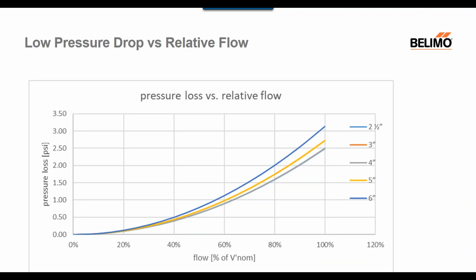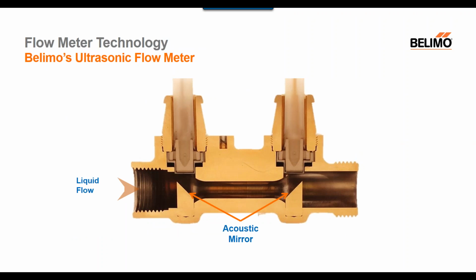Due to the ultrasonic technology and no moving parts in the flow sensors, the following graph highlights the low pressure drop for the largest size flow sensor versions. As you see, even at very low flow rates, we see minimal pressure drop for all sizes. And we also see very low pressure drop relative to the nominal flow. Again, minimal differences even between the varying sizes. Now let's take a look into more detail on the patented ultrasonic technology.